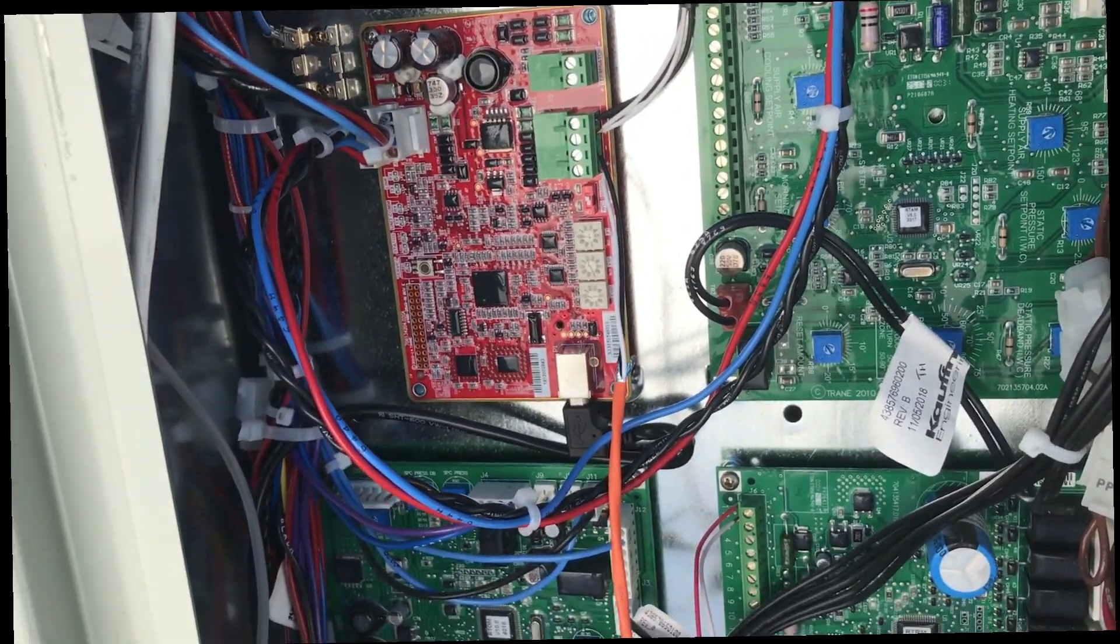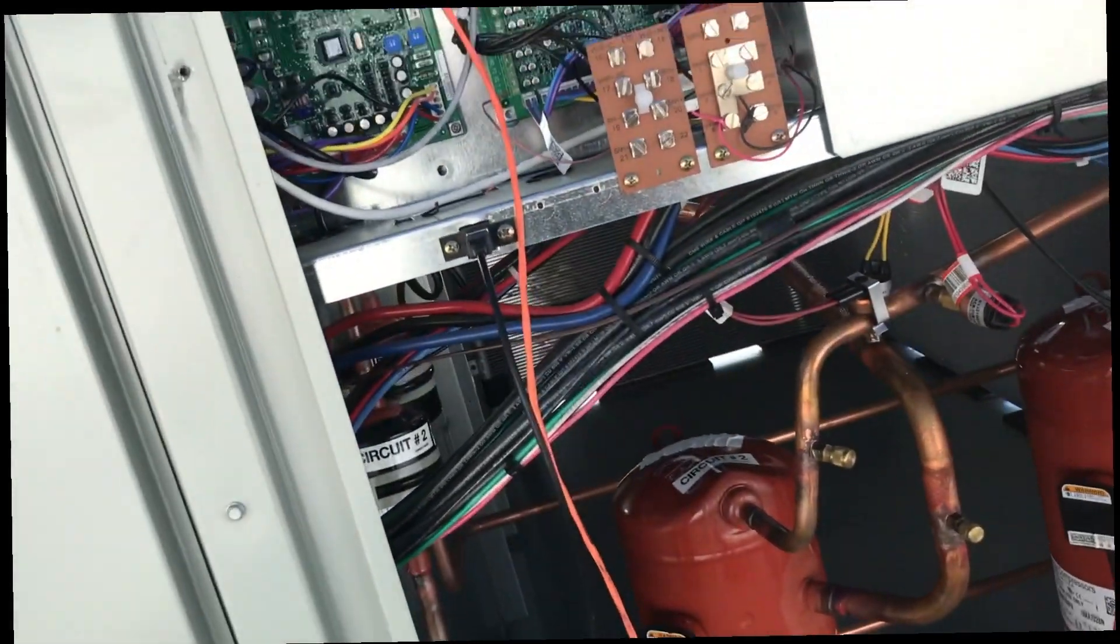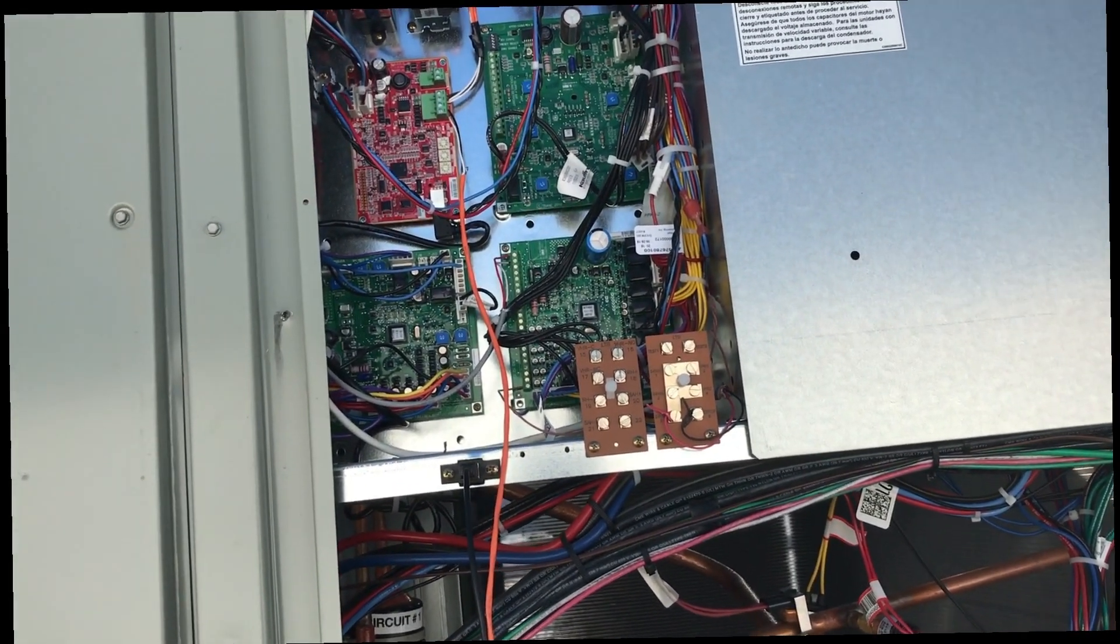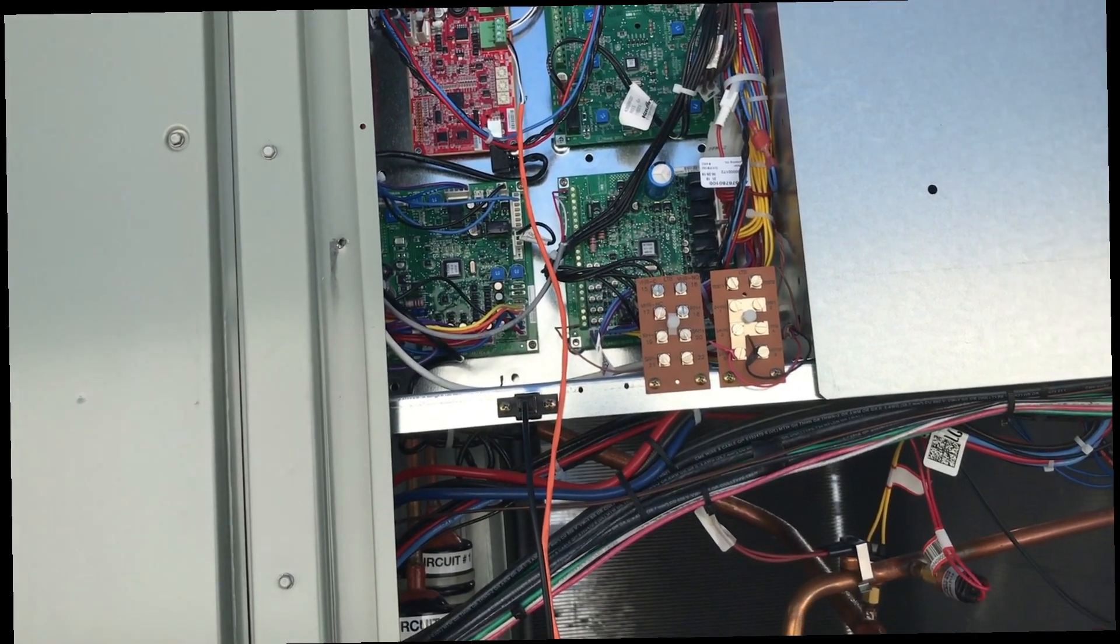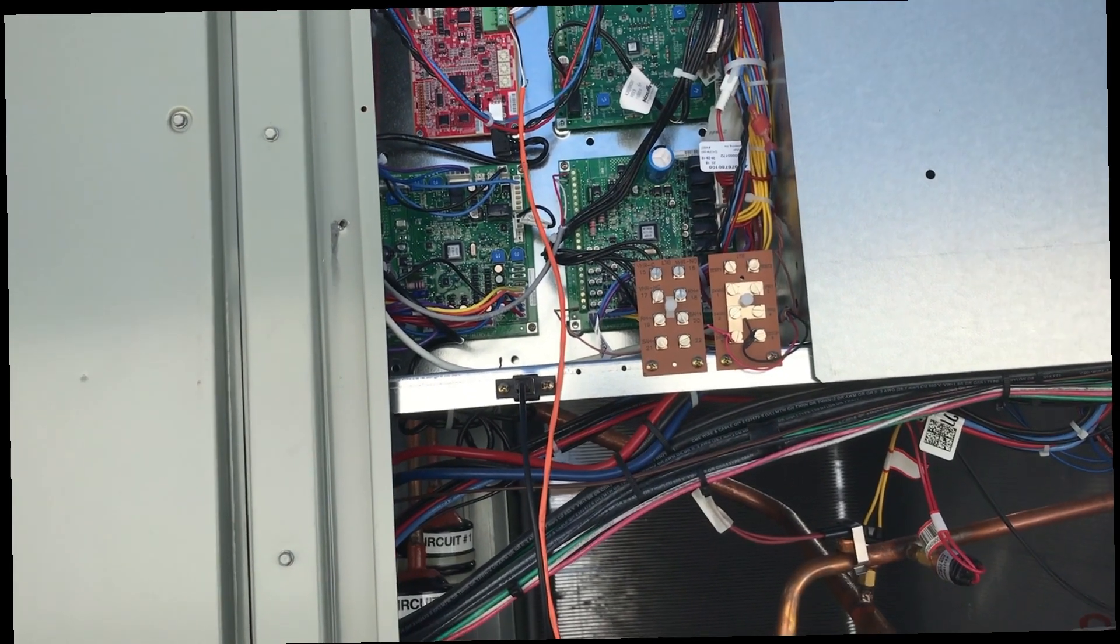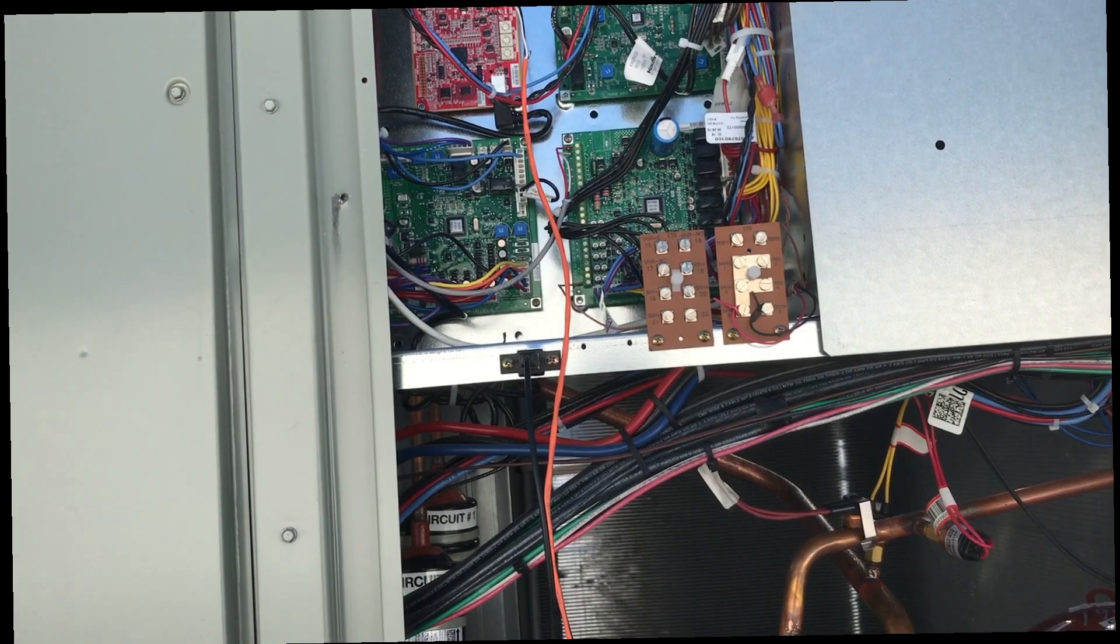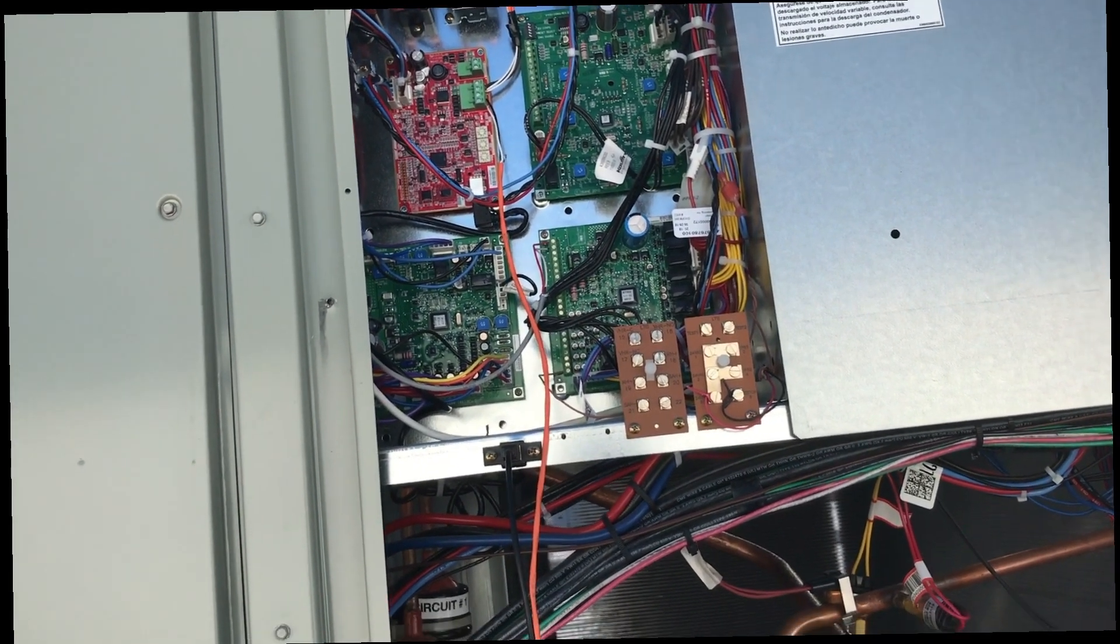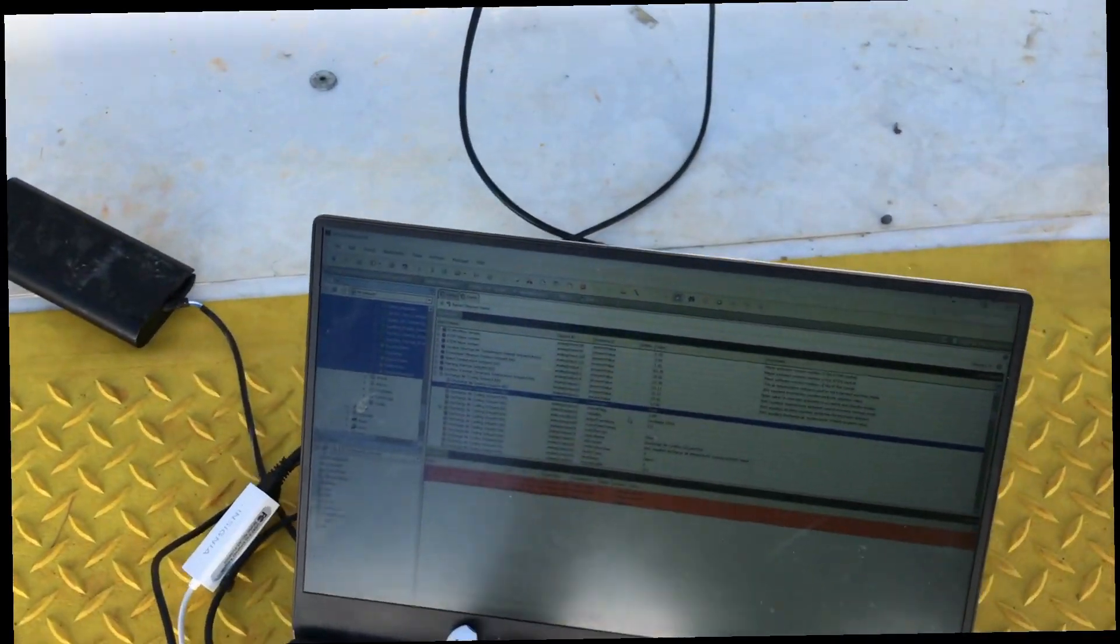So anytime you're working with these BCIRs and they're coming new, kind of like this, you've got to make sure that you have the Trane BACnet tool downloaded so that you can set stuff like the device ID, the unit conversion, which is the issue that we're having, and then the writable points, fun stuff like that. So I'm going to hop over here to the computer, show you the issue that I'm going through, and see if we can get it resolved.